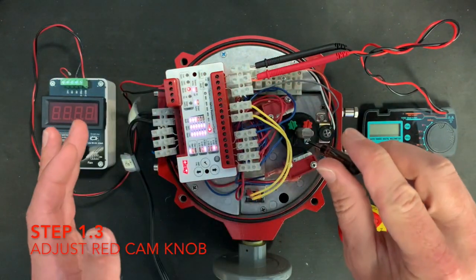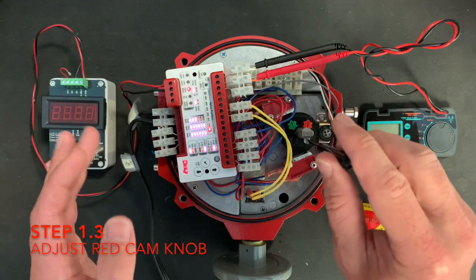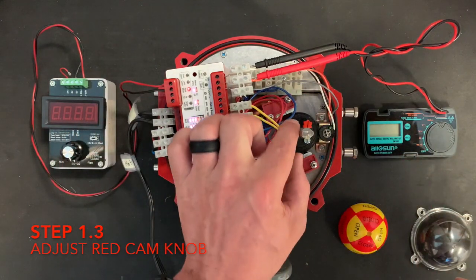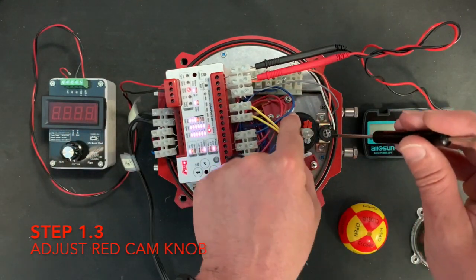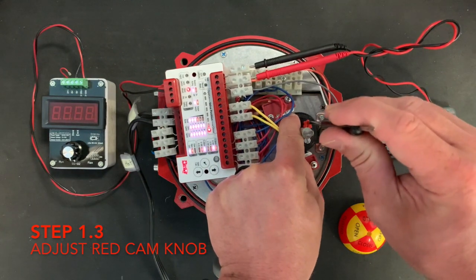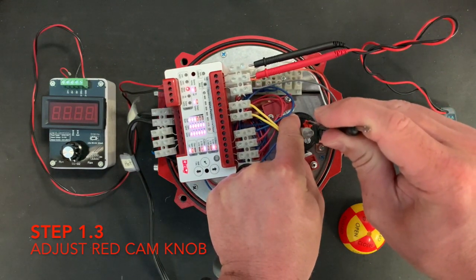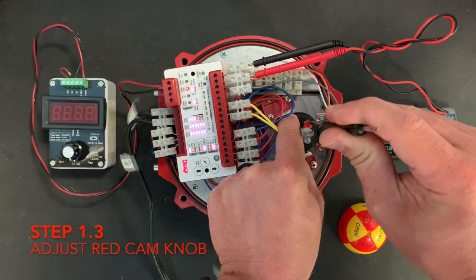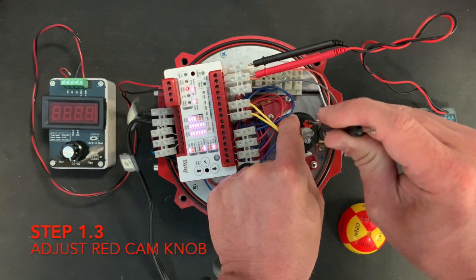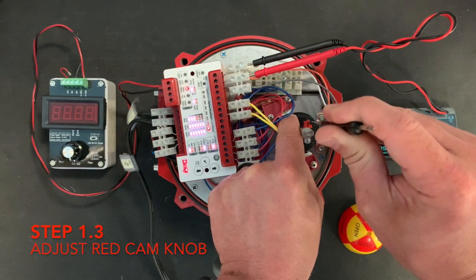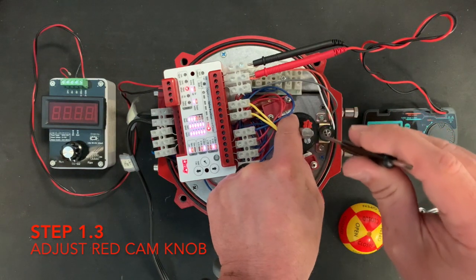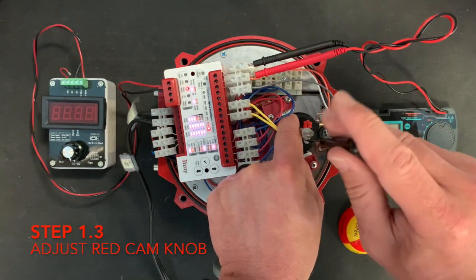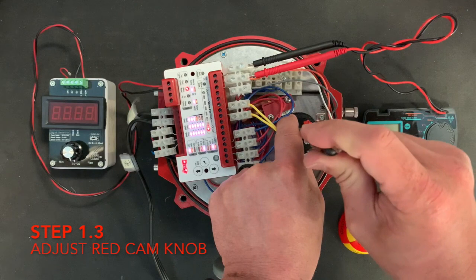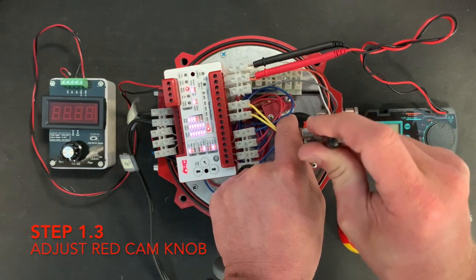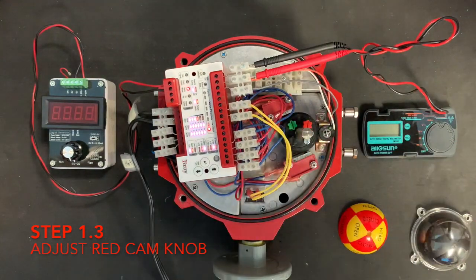Rotate the red cam adjustment knob with a flathead screwdriver until the cam lobe just activates, depresses, the switch from a clockwise direction. This can be accomplished by viewing the red valve position LED close light, or by listening for the second click sound from the travel limit switch. Note the first click sound comes from the auxiliary switch when applicable.